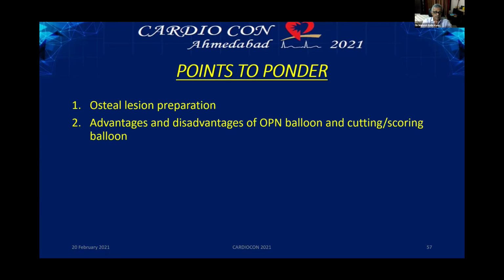My first case report with Dr. Haridas from Amrita was rupture of a cutting balloon inside the LAD, causing damage to the LAD and dissecting it. So it is not unusual that the cutting balloon also opens out and the blade opens out inappropriately and dissects the LAD, or they don't get deflated on time. So these complications are common to all the balloons that we use across the board.